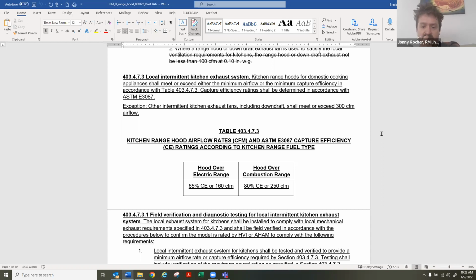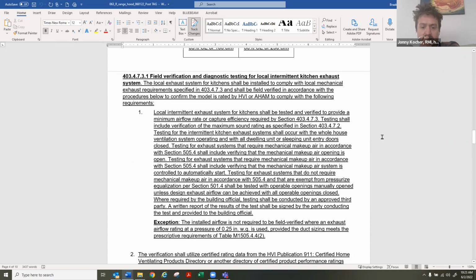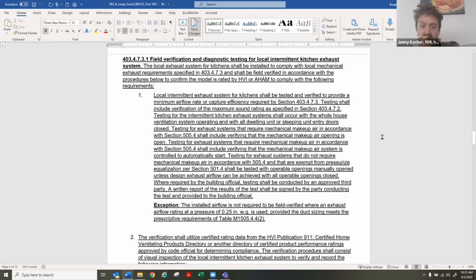And then I worked with folks on the field verification and diagnostic for the different exhaust systems according to 403.4.7.3.1. If you can scroll down, we just have some information here. If an exhaust system ends up requiring makeup air, I know Eric had a lot of concerns that if it doesn't require makeup air, there could be some sort of negative pressure. So we're saying that the testing must occur with an open window.